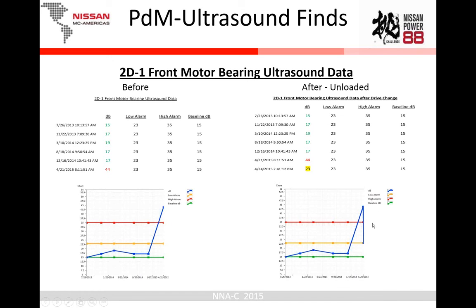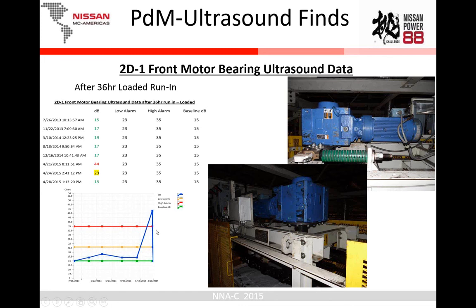After the replacement over here, they did replace that drive, and about 36 hours or 24 hours or so after it was replaced, I took another reading on it, and the decibel levels dropped down, on that motor front, to about 22.5 dB. Then after it had run in pretty good - this is the drive - but after it had run in about 36 hours, after it's been run in and loaded down and put in its normal operation, it dropped all the way back down to baseline. It couldn't have been any more picture perfect than that.